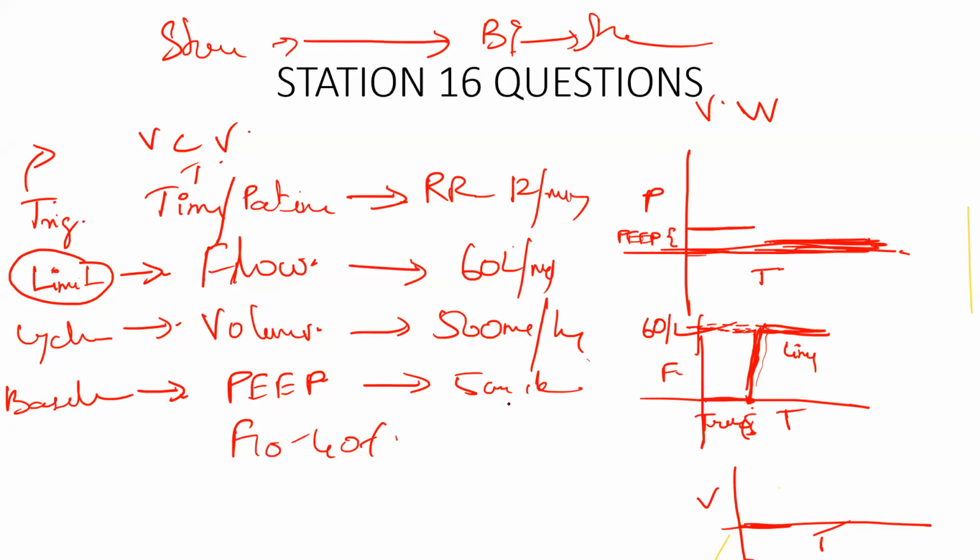Okay. Now it has blown air into the patient's lung. What happens to the pressure? It will rise. It will go up. So during this continuous airflow, the pressure will rise in the ventilator. It will go up. So what is this point? This is called the peak inspiratory pressure. Okay. Yes, sir. Guys, if you don't understand any point, let me know. Understanding this is important to interpret the waveform.